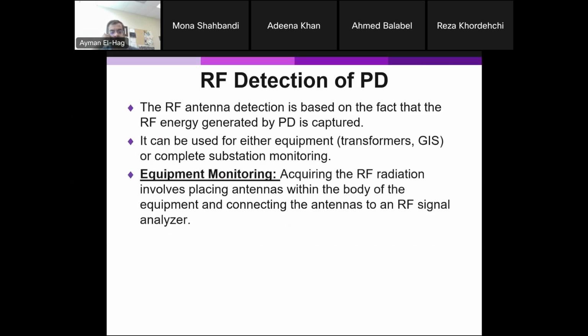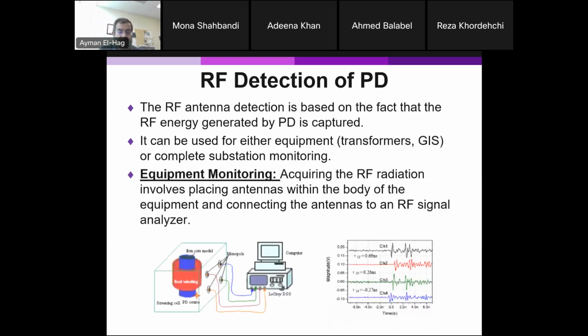Now, if you use it for equipment monitoring, okay, you need to have the antenna inside the device. You cannot have the antenna outside the transformer because the transformer tank will shield any electromagnetic waves from inside. It acts like a Faraday cage. So you have to basically insert the antenna inside the transformer.